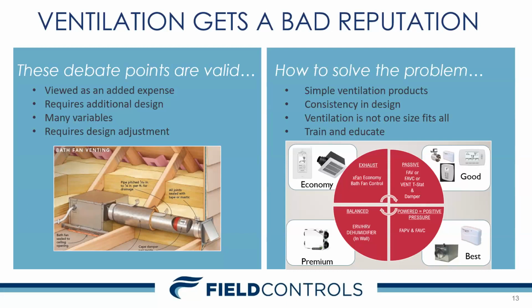ventilation. Exhaust ventilation is what you see on the right, typical bath fan that is only exhausting air from the home. Passive ventilation, which may be just an open duct that a damper would open whenever the air handler goes on. Typically, those are not good setups because they tend to overventilate the home, especially in more southern climates. That's when you come up with a lot of issues. We've seen water in dryer vents. We've seen any type of kitchen ventilation pulling in microbial growth. So passive is an option for a certain climate zone, but it doesn't fit the southern climate.